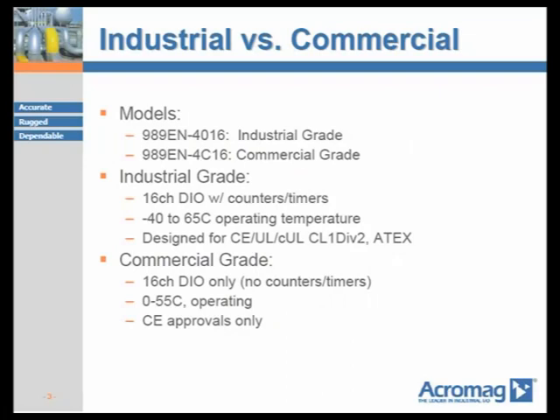The 989EN is offered in two basic models: industrial grade and commercial grade. Model number 989EN-4016 is an industrial grade discrete I/O device that includes 16 channels of discrete I/O that can be used in any configuration of inputs and outputs. The I/O can also be used as configurable counters, timers, and alarms. It is designed for extended operating temperatures of minus 40 to 65 degrees Celsius, and is designed to meet CE, UL, CUL, Class I Division II hazardous locations, and ATEX Zone II approvals for European hazardous location requirements.